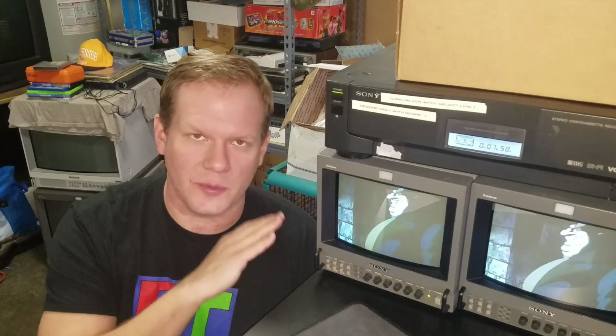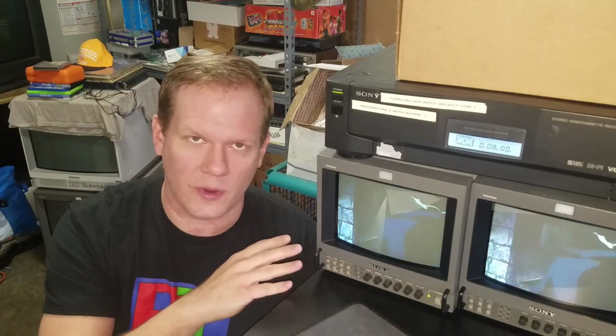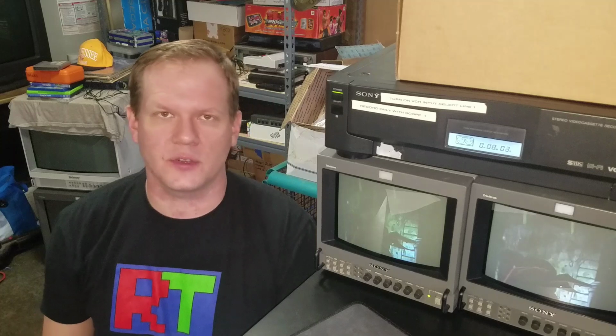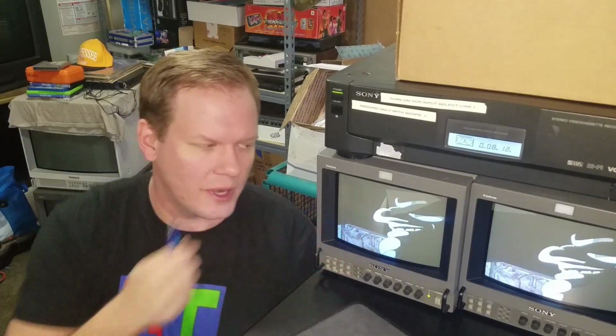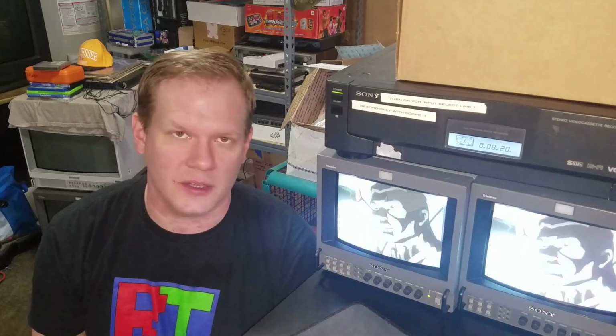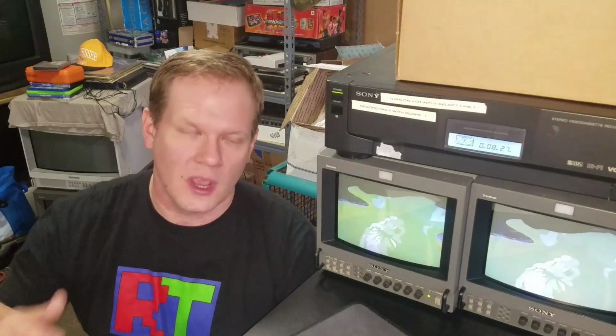There's also a humidity limit on a lot of these, a warning where it can go up to 90% humidity on storage. You really want to try to avoid condensation of any type when using or storing these PVMs or any CRT. What I mean is, if you're in an environment like my shop, occasionally humidity will get really high and temperatures might change rapidly, and then you've got almost a mist in the air. It's not really safe to store or use the PVMs in that environment.